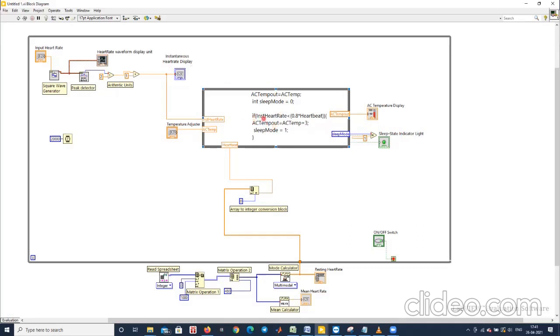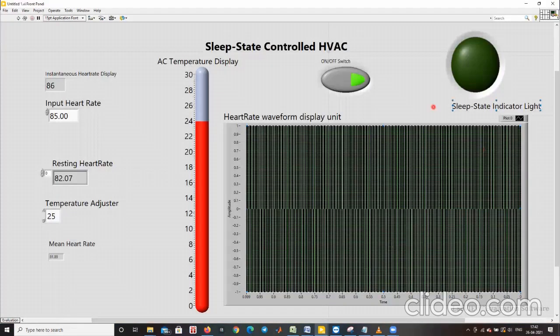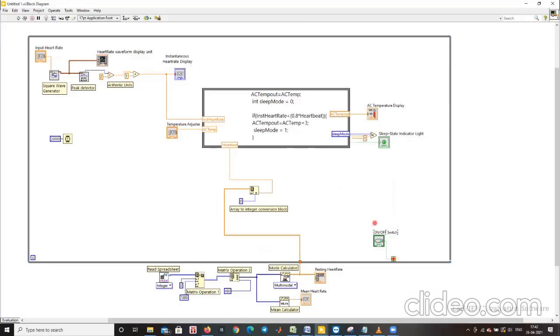And there are a few auxiliary components or blocks also. First is this timer block, which is at 20 seconds. And second is this on and off switch. So first we'll look at the on and off switch. This basically is the same. This is connected to this switch on the dashboard, which turns on and turns off the system. This 20 seconds here is this whole gray color rectangle here. This whole block is activated every 20 seconds.